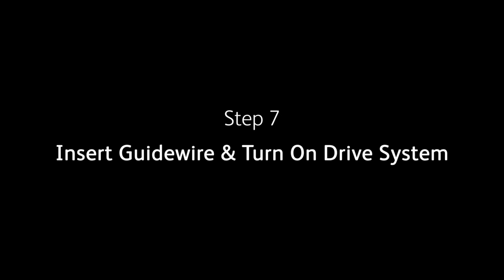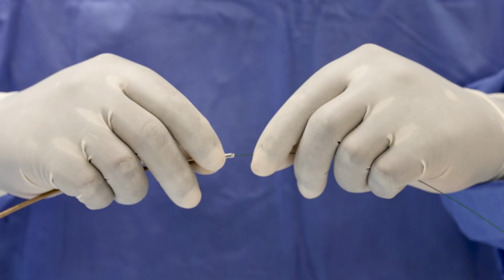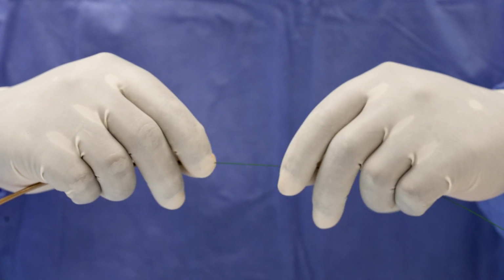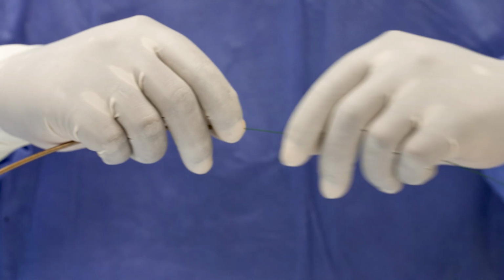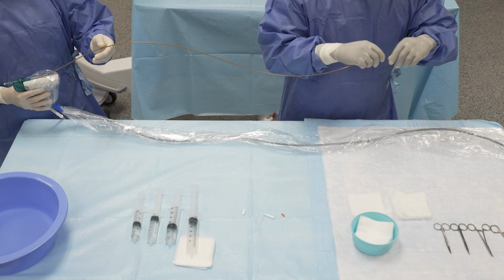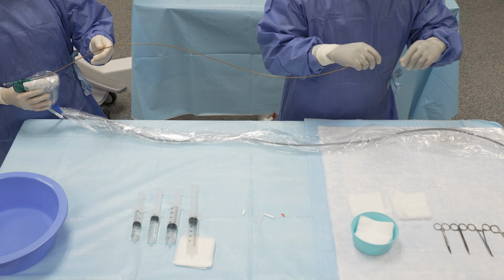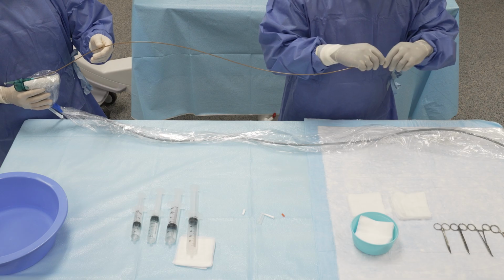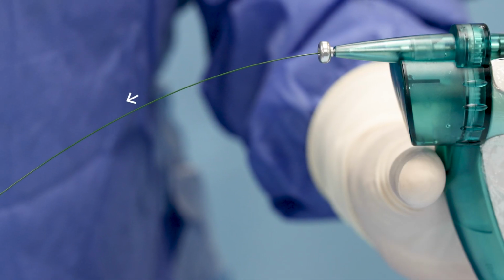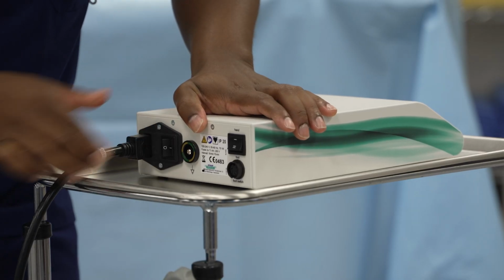Step 7. Insert catheter and turn on drive system. Ensure the Aspirex guide wire is correctly positioned before inserting and activating the catheter. Feed the Aspirex catheter over the guide wire. Once the catheter is fully over the guide wire, and before inserting into the sheath, switch on the drive system.